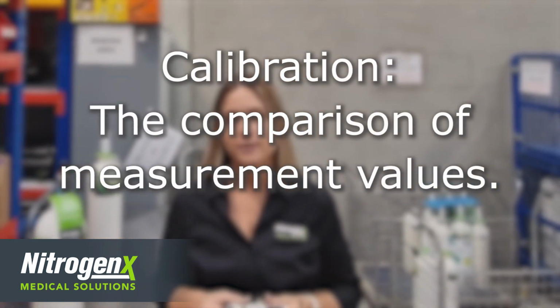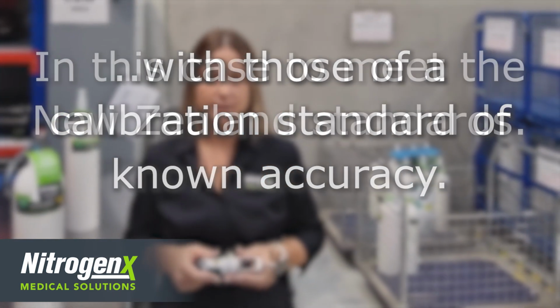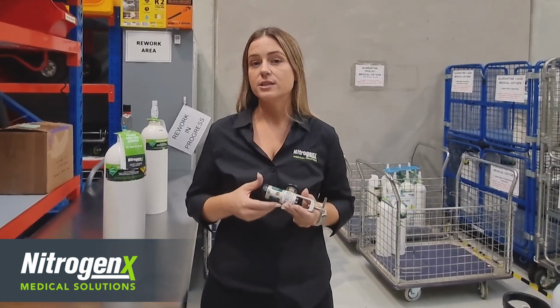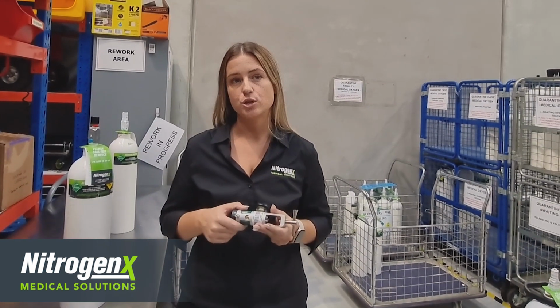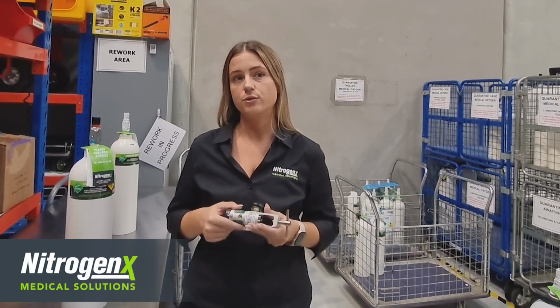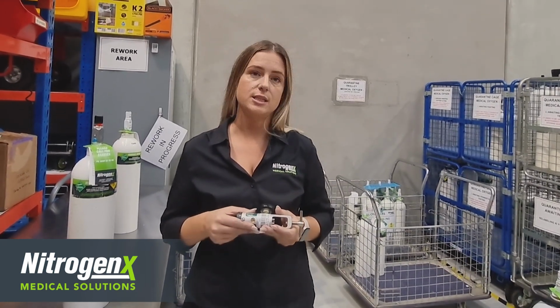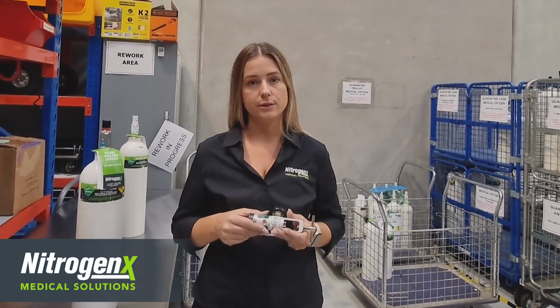Calibration is the comparison of measurement values delivered by a device under test with those of a calibration standard of known accuracy, in this case to meet the New Zealand standard. So effectively, it's testing the regulator to make sure it continues to meet the above New Zealand standards and work as intended when used with medical oxygen delivery.